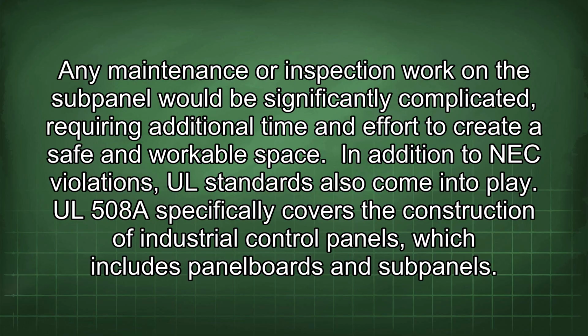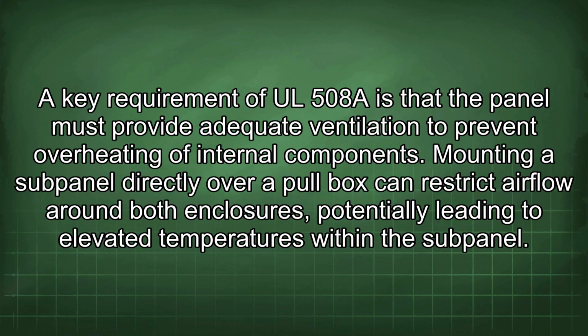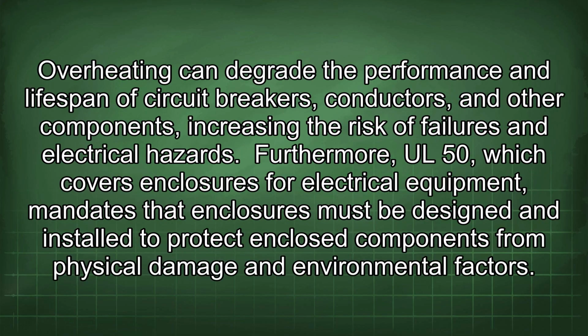In addition to NEC violations, UL standards also come into play. UL 508A specifically covers the construction of industrial control panels, which includes panelboards and subpanels. A key requirement of UL 508A is that the panel must provide adequate ventilation to prevent overheating of internal components. Mounting a subpanel directly over a pull box can restrict airflow around both enclosures, potentially leading to elevated temperatures within the subpanel. Overheating can degrade the performance and lifespan of circuit breakers, conductors, and other components, increasing the risk of failures and electrical hazards.